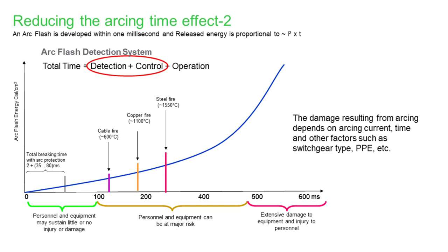When dealing with an arc flash detection system, the total time includes detection time, control time, and breaker operation time. What we can control in our system is the detection and control portion. Our target: if we can detect the arc within 2 milliseconds and add breaker operation time of 3 to 5 cycles, we are targeting around 80 milliseconds maximum. That's a good target to apply the arc light system.